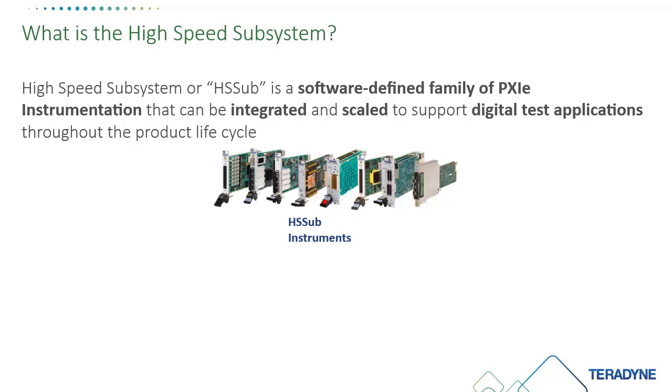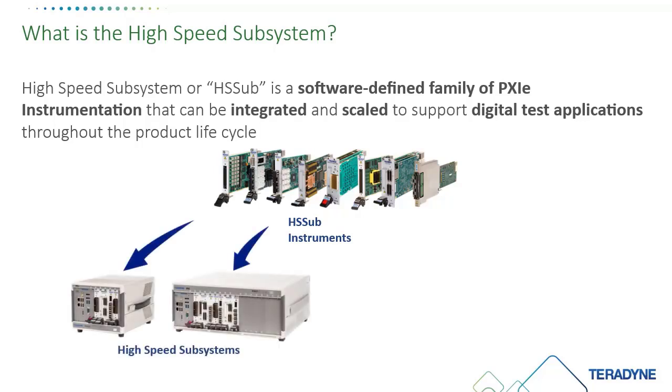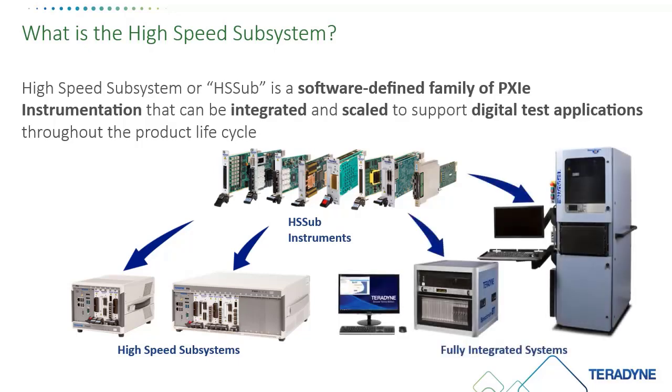The High-Speed Subsystem, or HSSub, is a software-defined family of PXI Express instrumentation that can be integrated and scaled to support digital test applications throughout the product lifecycle. HSSub instruments can be integrated together into a PXI-E foundation for autonomous operations or be added into existing ATE systems.